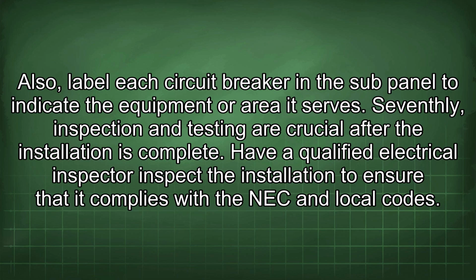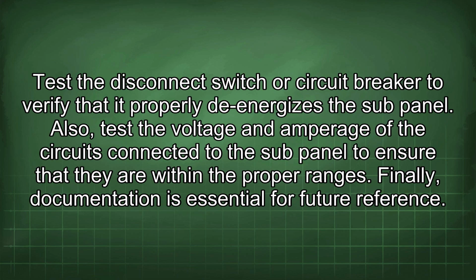Seventhly, inspection and testing are crucial after the installation is complete. Have a qualified electrical inspector inspect the installation to ensure that it complies with the NEC and local codes. Test the disconnect switch or circuit breaker to verify that it properly de-energizes the sub-panel. Also, test the voltage and amperage of the circuits connected to the sub-panel to ensure that they are within the proper ranges. Finally, documentation is essential for future reference.